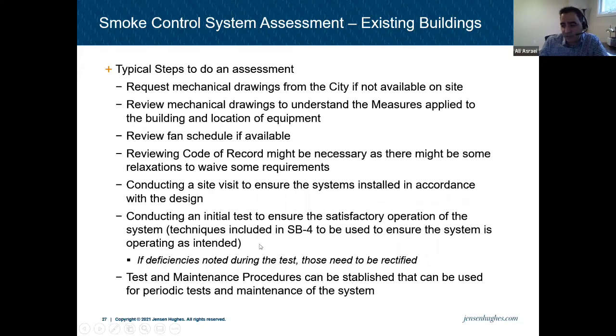It is just to make sure that the system performs properly, with satisfactory operation. Again, there are techniques in SB4 we use to make sure that the fan or the whole smoke control system works properly. If there are deficiencies, they need to be rectified at this stage before we can give them a procedure for maintenance, right? The first step is just to make sure, and the fire code says satisfactory operation. If you're not satisfied with the operation of the system, then we can't give them that. They have to fix this first, and then we can maintain the system after that.